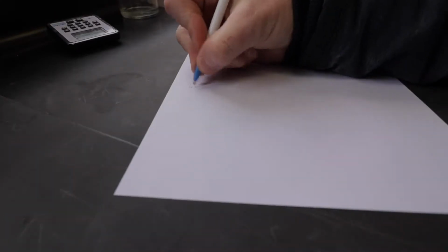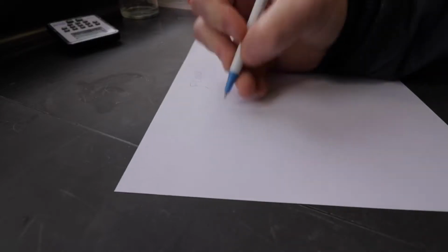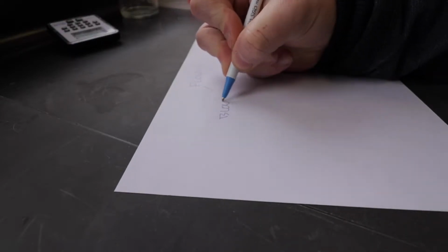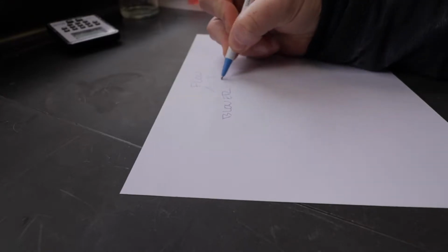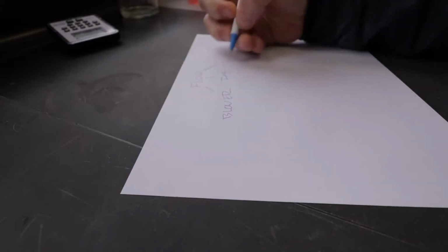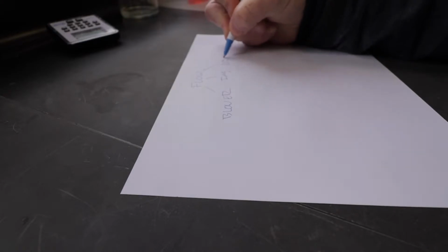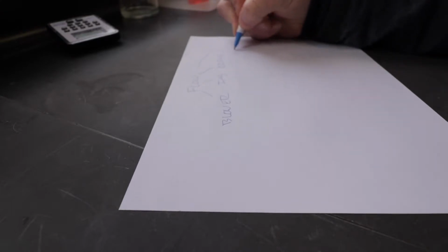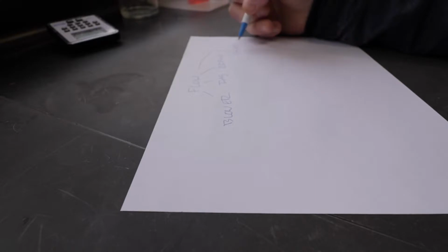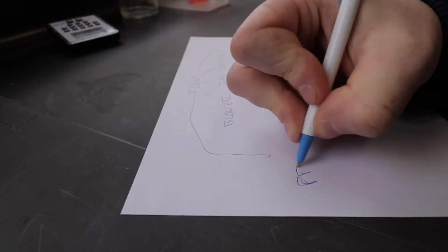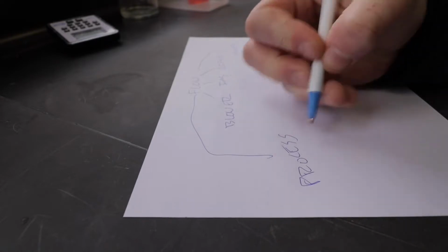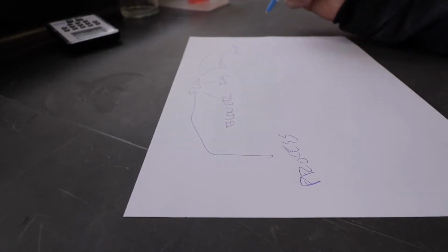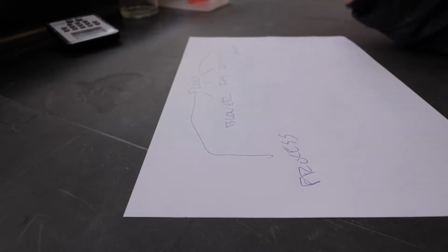For our airflow, it's pretty simple. We have a flow measurement. That flow measurement comes from a blower. There's an instrument that's measuring that flow. There's the diffusers themselves. They could be fouled. There's the valves and actuators. There's also the process. Now, I don't have to break these down too much farther because right now I need to get started on identifying these parameters. So we called the instrumentation techs and we had them pull and verify the flow meters.